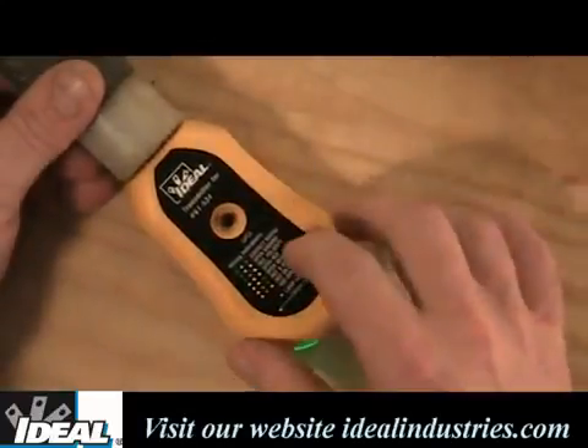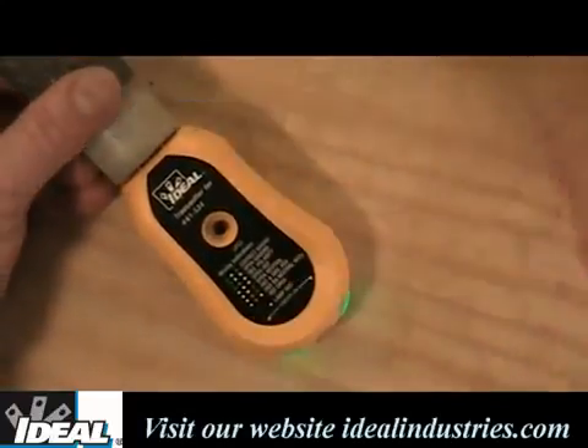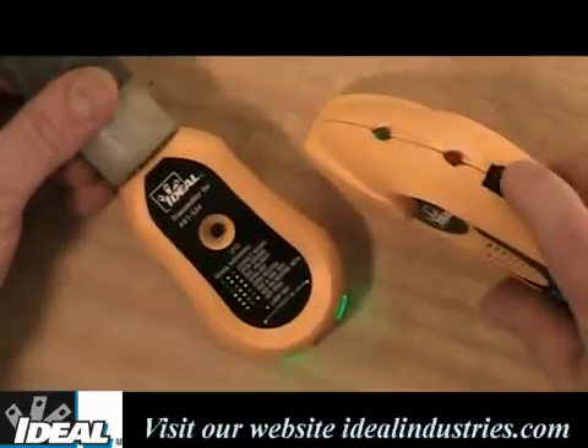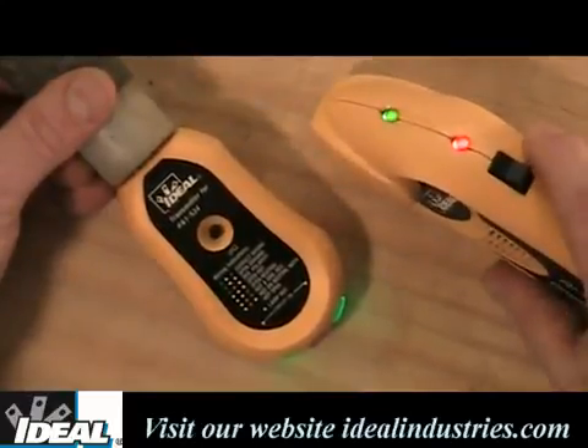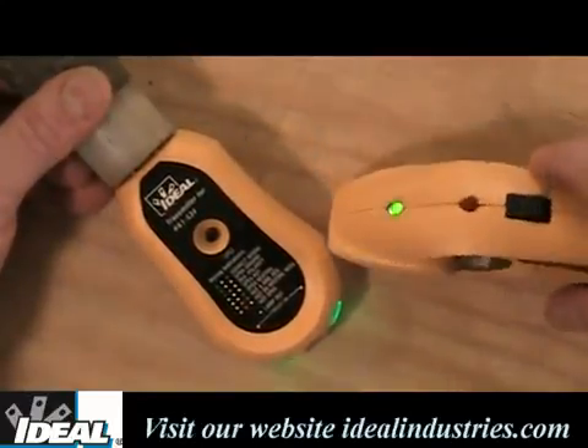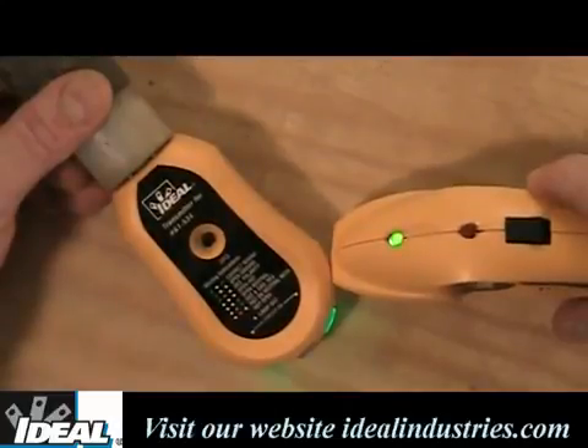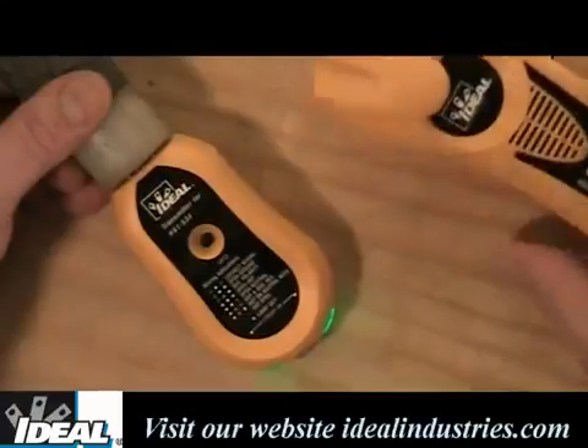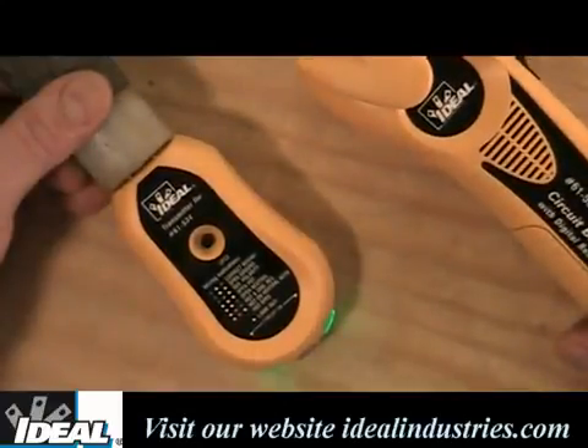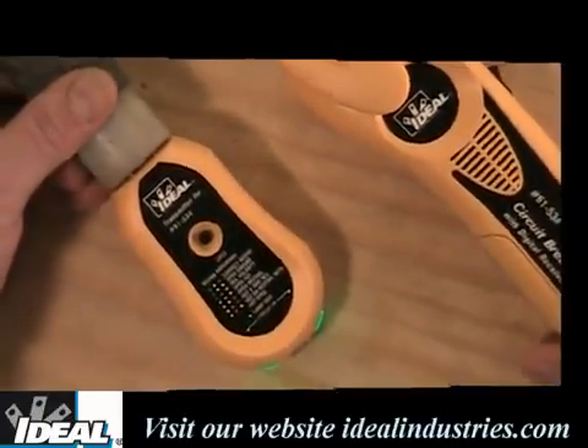This transmitter is generating a tone that the tracer, or receiver unit, is designed to find. If I turn my receiver on and hold it up against it, sure enough, it's making a sound, and we're going to use that to go locate that breaker back inside the panel. Let's go trace this circuit and find that breaker.